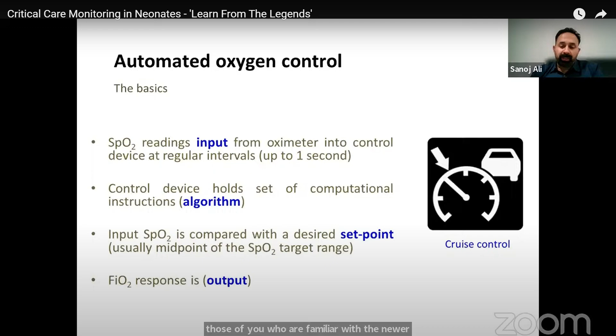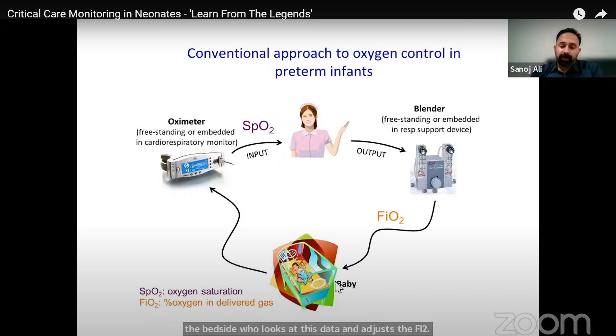We have the baby, the pulse oximeter connected to the baby gives the data. We have a lovely nurse at the bedside who looks at this data and adjusts the FiO2 on the ventilator or on a standalone oxygen blender. And this is what is delivered to the baby. And if you look at what automated oxygen control is, all you do is substitute the nurse with an algorithm which is housed within the ventilator or connected to the blender.